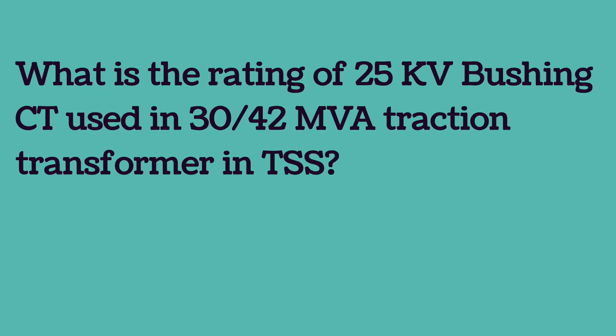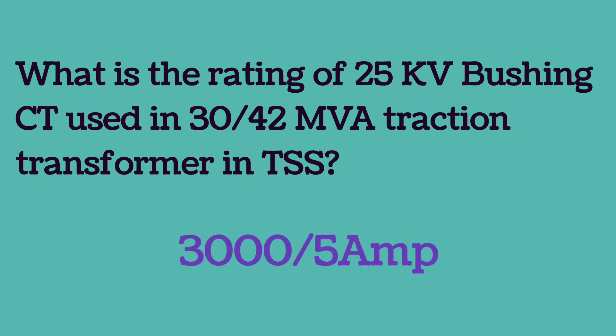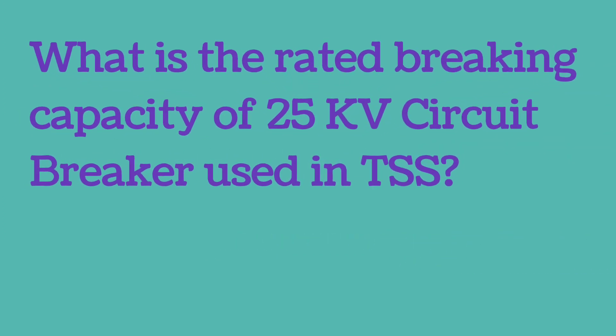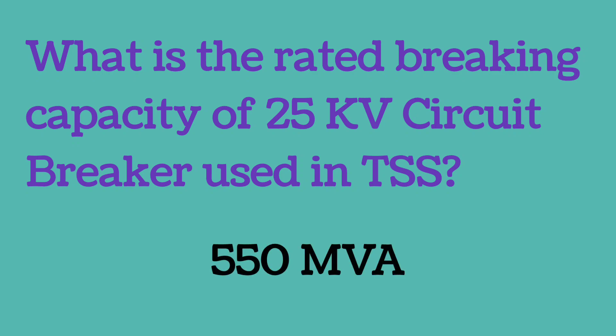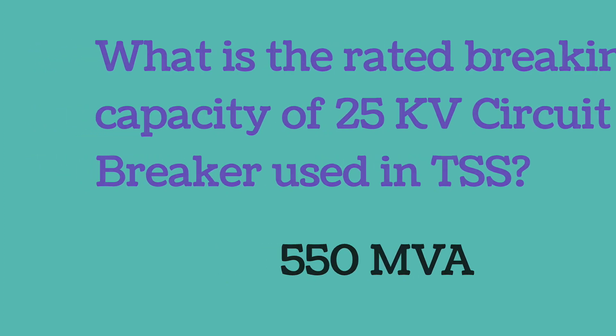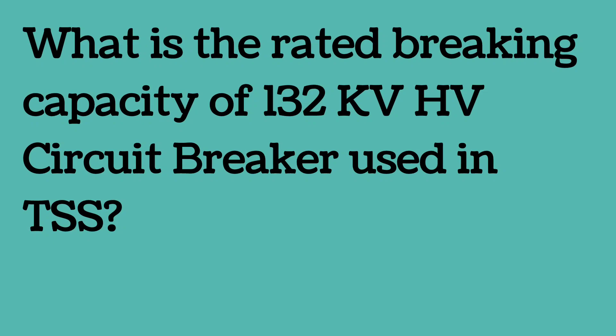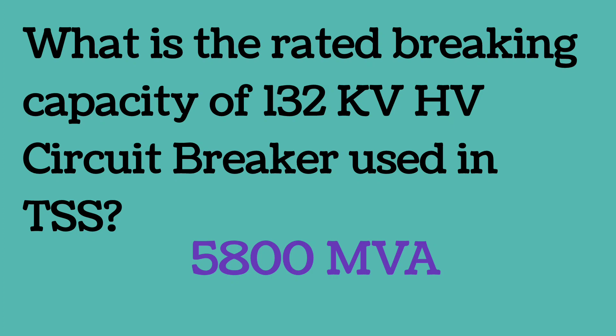The rating of 25 kV bushing CT used in a 30/42 MVA traction transformer in TSS is 3000/5 Amp. The rated breaking capacity of a 25 kV circuit breaker used in TSS is 550 MVA. The rated breaking capacity of a 132 kV circuit breaker used in TSS is 5800 MVA.